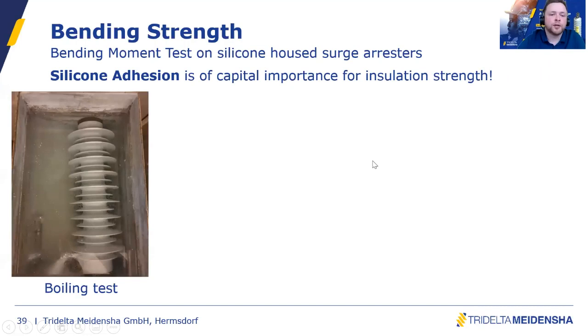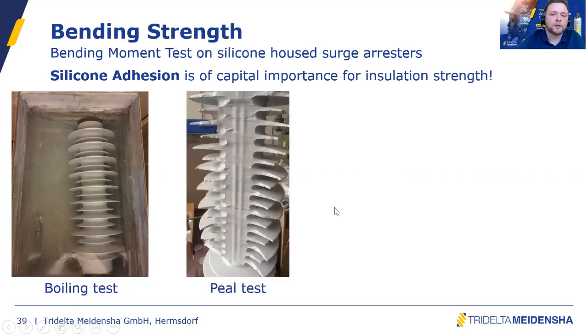So we are doing a boiling test. The surge arrestor is held under boiling salt water for 42 hours. So that's a very, very harsh condition for the surge arrestor. And afterwards we do an electrical measurement. But what we also do is a peel test. So this is what we provide during our normal manufacturing. This is a quality test we conduct internally. It's not standardized, but it's a kind of quality assessment.